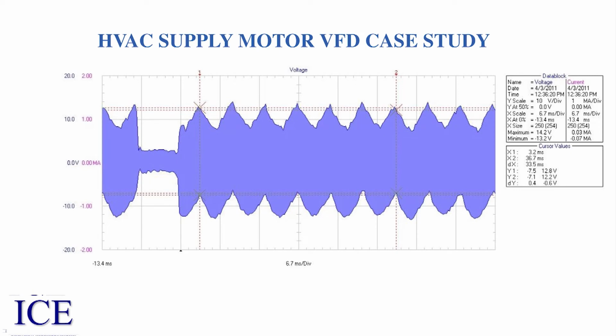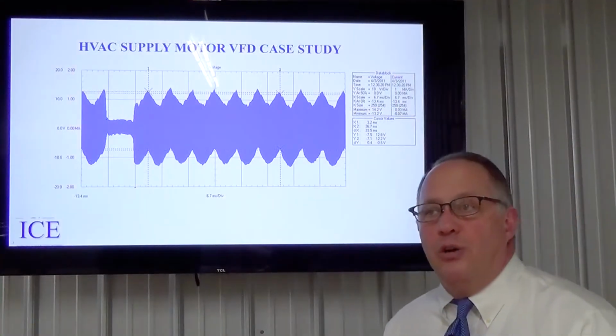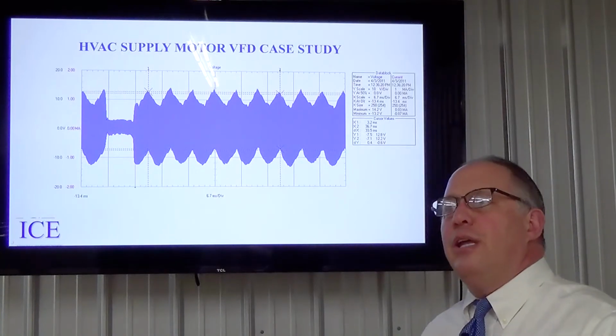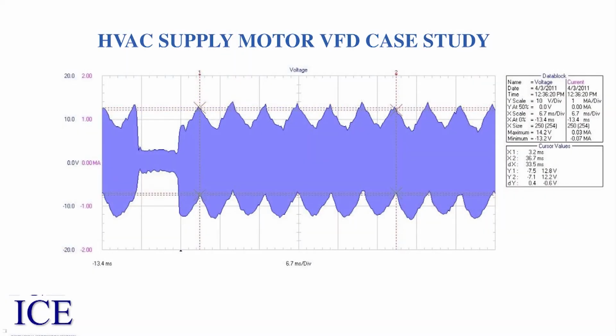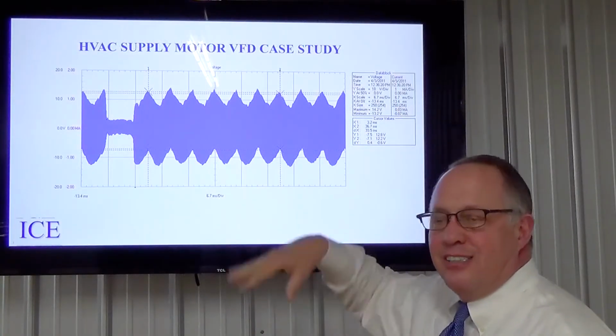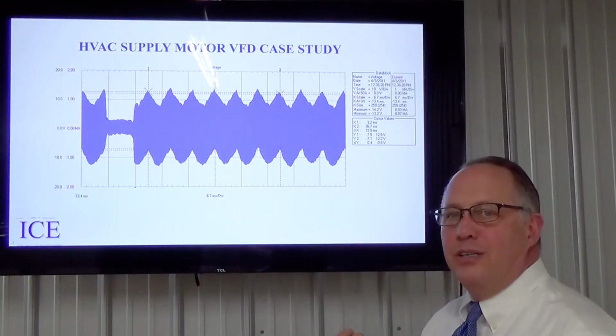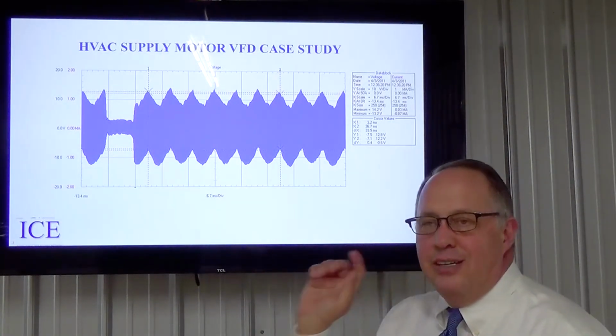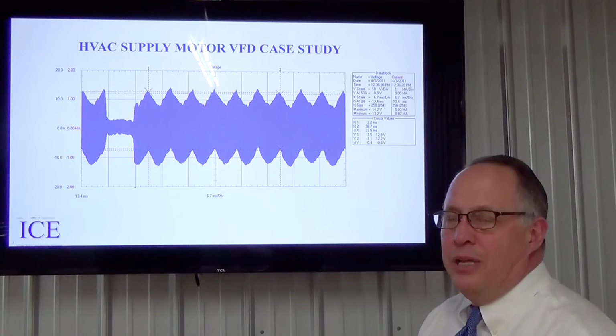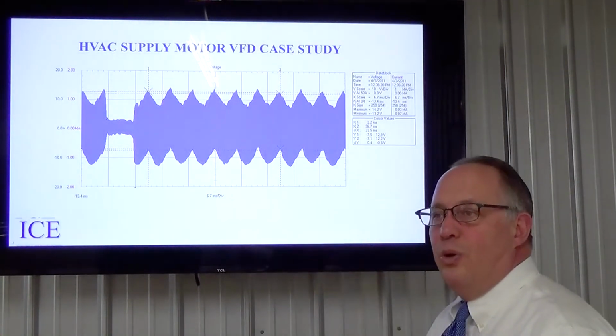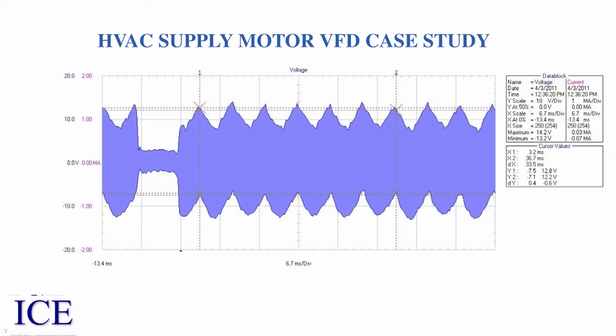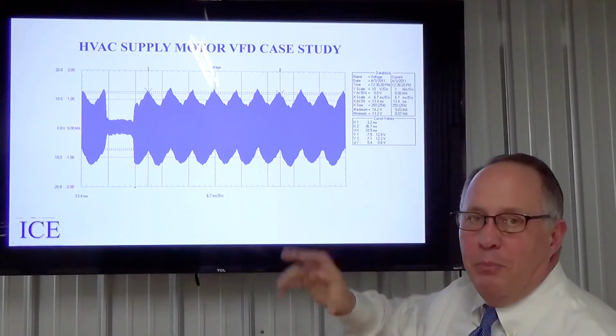Number 2, HVAC supply motor VFD case. This was a motor at a university, between 30 and 50 horsepower is what it was used for. And this particular motor, we can see that even with 6.7 milliseconds per division, it's essentially a solid line. In other words, the frequency at which it was operating and the discharges into the shaft were incredible. We estimated this motor was going to last about 3 months. That's it. It had already deteriorated to that point, even though the voltages were only about 12 to 13 volts, 26 volts peak to peak.